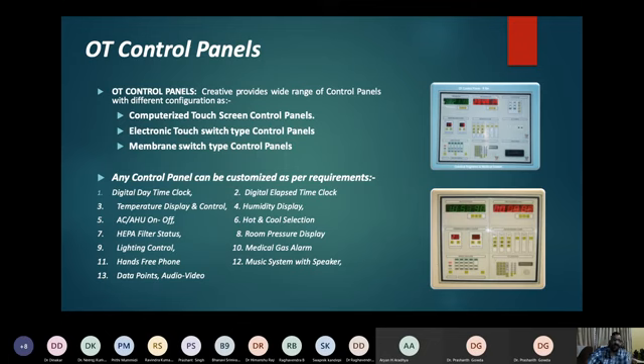Coming next to the OT control panel. In all modular OTs, there will be a control panel. There are multiple types of control panels available: the computerized touchscreen control panel, which is the high-end one, then electronic touch switch type panels, and the third, which is the most common, the membrane switch type control panel. The second picture shown is what is normally used in most modular operation theaters.